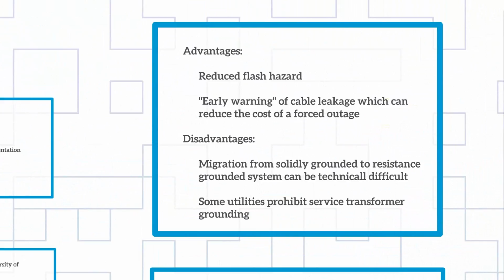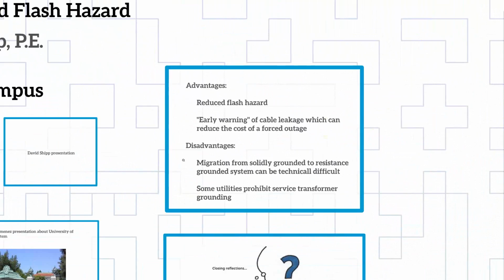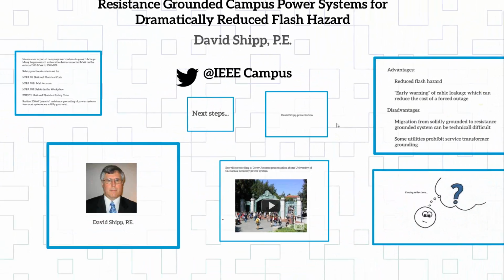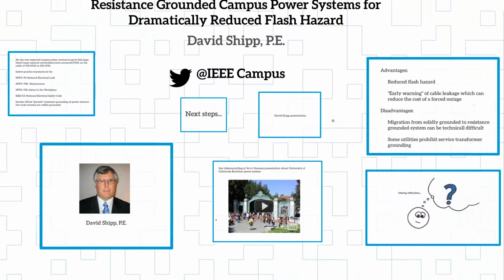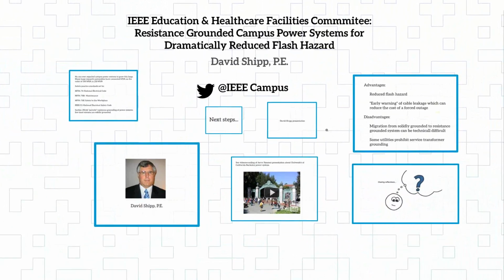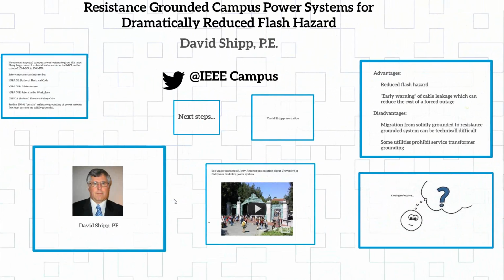Now, when I go to resistance grounding, remember the incident energy, and I'm not going for arc flash energy where you size it on the three-phase fault. I'm not just talking about an individual single-phase one. 70 to 80% of all faults that occur start out as a single-phase to ground arc fault event, and medium voltage is no different. It's maybe 70 to 80% of the three-phase bolted fault or the maximum available with one phase. But it's one phase. It's not three of them. Now, if you leave it on long enough, a few cycles, 0.1 seconds, something like that in a confined space, it will then escalate to a three-phase bolted fault if I don't clear it or do something.